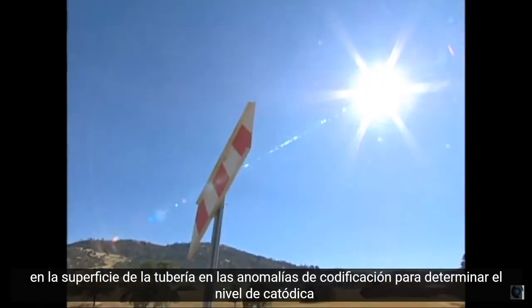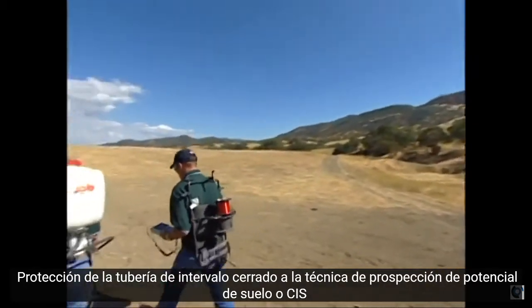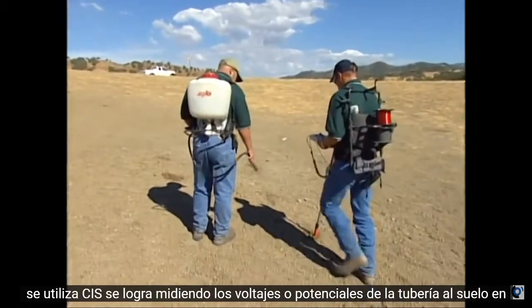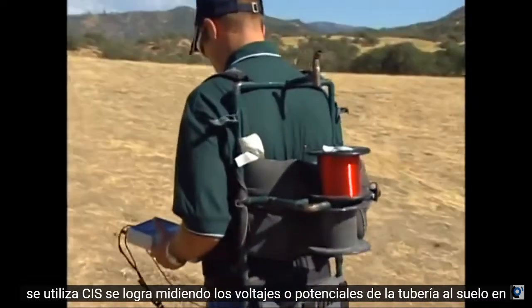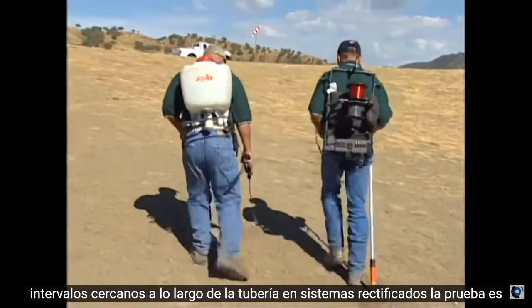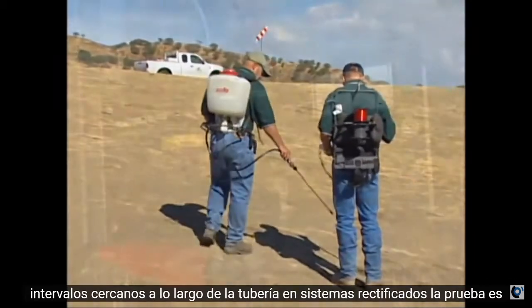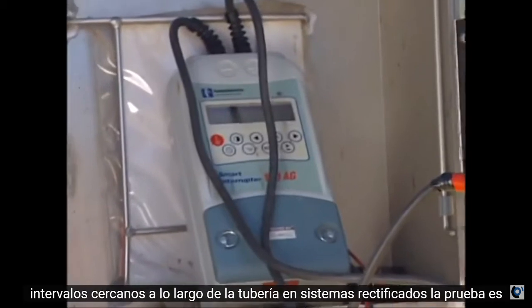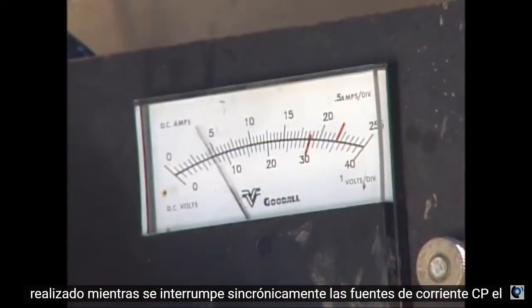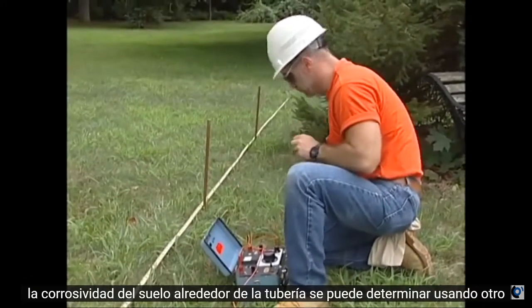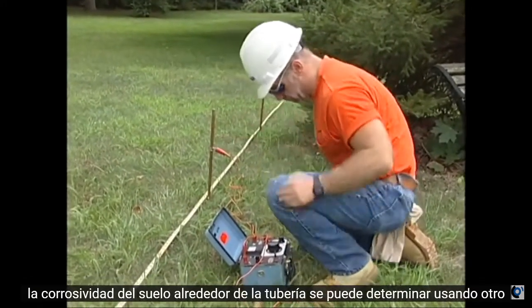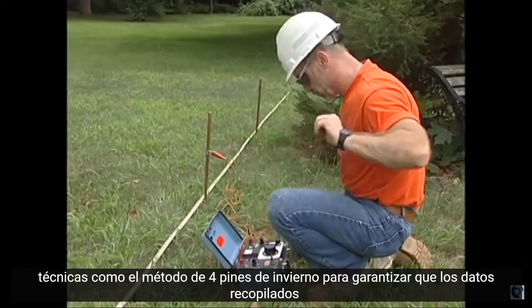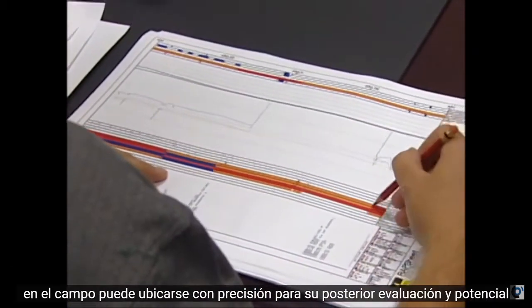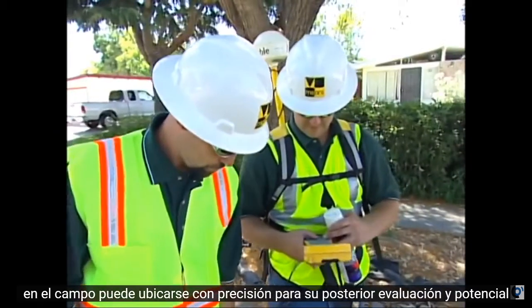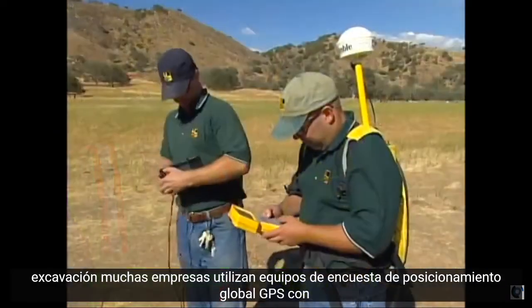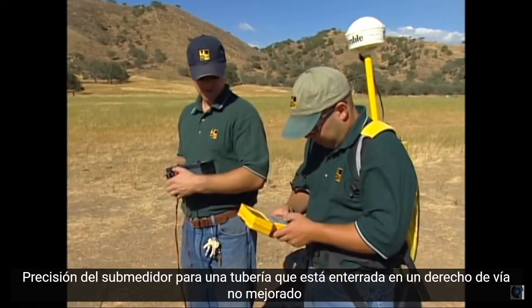To determine the level of cathodic protection, the Close Interval Pipe-to-Soil Potential Survey Technique, or CIS, is used. CIS is accomplished by measuring pipe-to-soil voltages, or potentials, at close intervals along the pipeline. On rectified systems, the testing is performed while synchronously interrupting the CP current sources. The corrosivity of the soil around the pipeline can be determined using other techniques, such as the Wenner four-pin method. To ensure that the data collected in the field can be accurately located for subsequent evaluation and potential excavation, many companies use Global Positioning System equipment, GPS, with sub-meter accuracy.